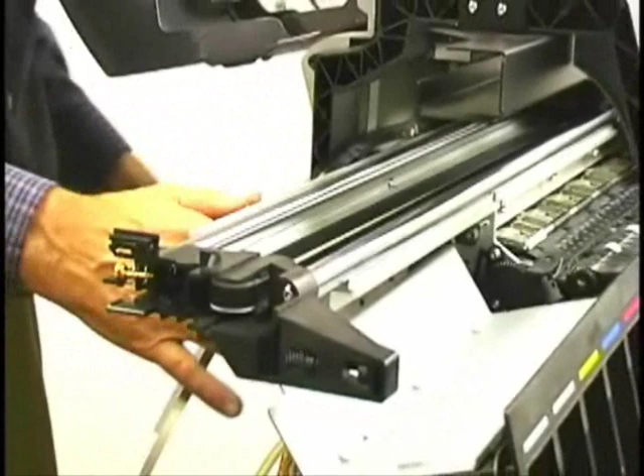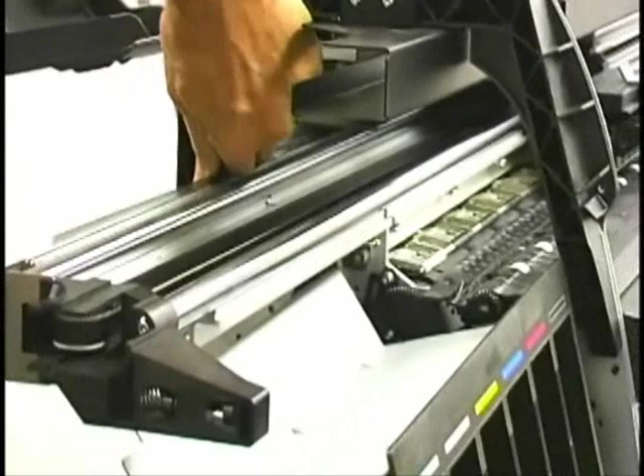The next part is to put this encoder strip back on. The lug obviously goes to the outside here. It fits back into the machine with some little pegs. We'll do just the opposite of what we did when we took it off, and that's compress that and put it on. There's a nut that goes on here, which I have misplaced — we'll get to that in a minute. You need to look down through the machine and make sure that the encoder strip is completely vertical the whole way down and in properly.